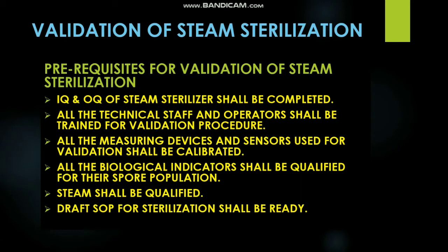All the measuring devices and sensors used for validation shall be calibrated. So whatever RTD probes, stopwatches, and dual timers are there in sterilizers, all these things should be calibrated and qualified. All the biological indicators shall be qualified for spore populations. In steam sterilization we are using biological indicators also, so they should have a proper population qualification, that is, the number of spores available should be determined, and it should be within acceptance criteria.